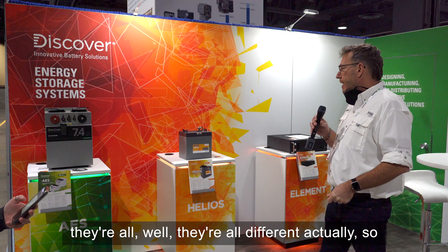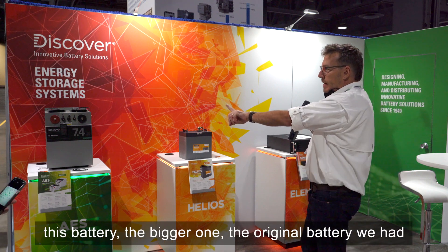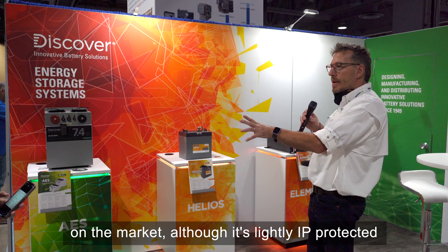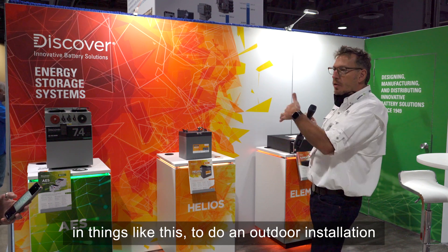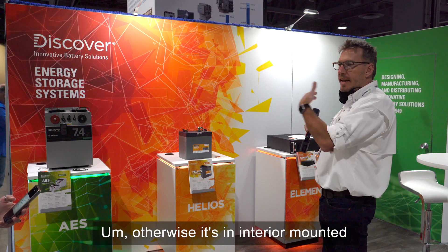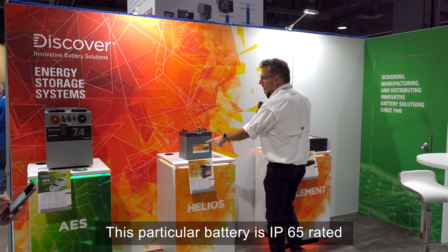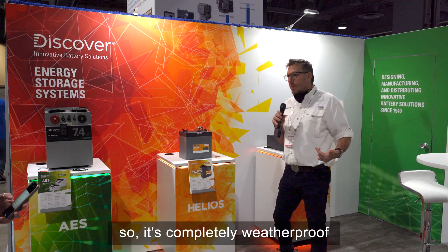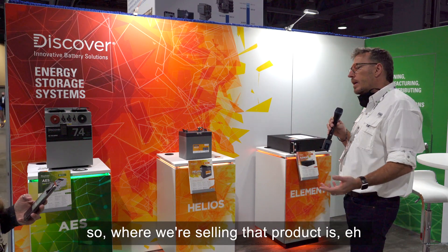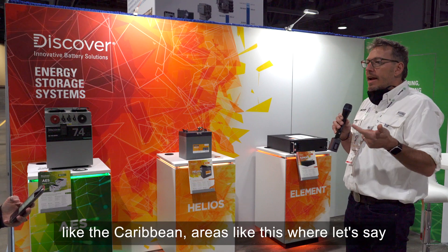They're all different though. The bigger original battery, although lightly IP protected, requires a cabinet for outdoor installation — otherwise it's interior-mounted in a humidity-free environment. This particular battery is IP65 rated, so it's completely weatherproof and could even be immersed in water.